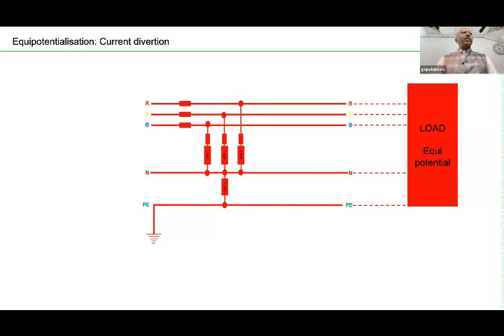But there are new principles applied in the upcoming standards. You can see that there is a reflection phenomenon. Reflection phenomenon means there is a surge arrestor and its effect is probably maybe 20 meters. After 20 meters, there can be an effect. So that means multiple SPDs are required. But in a simple understanding, if the wires are made in this way and if these wires are shielded, let's say going through a metallic conduit, under that condition your equipment is safe.